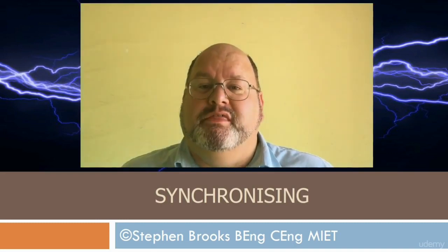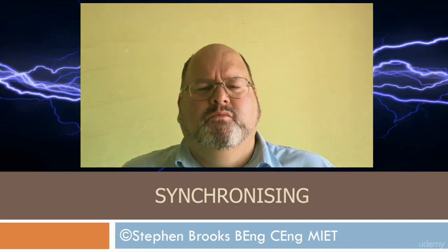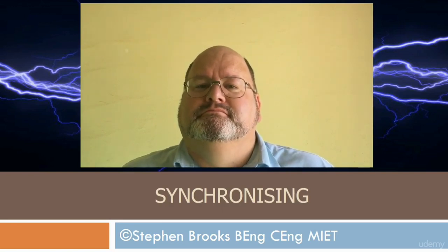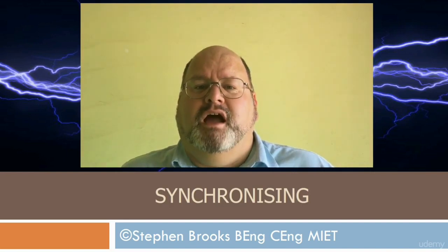Congratulations for making it halfway through the course. When we close circuit breakers, we have to ensure that the two systems that we are connecting together have similar parameters, otherwise the circuit breaker may get damaged. To do this, we use synchronizing equipment. By the end of this section, you will understand all of the parameters we need to check before closing a circuit breaker, and what equipment and circuits we use to ensure that the circuit breaker is closed safely.